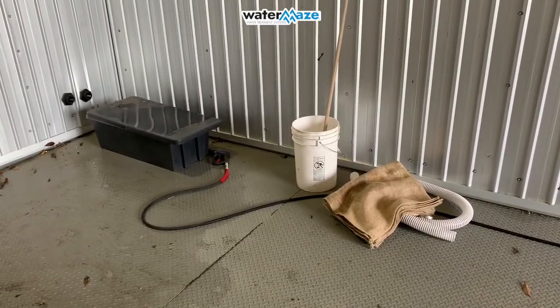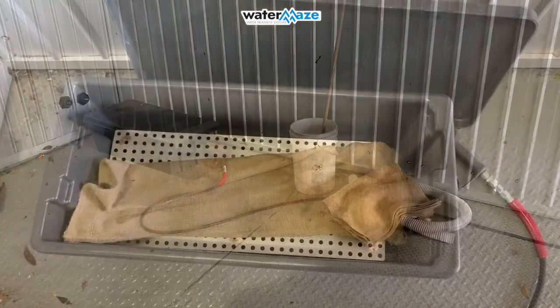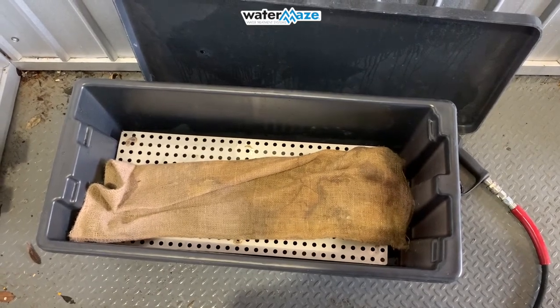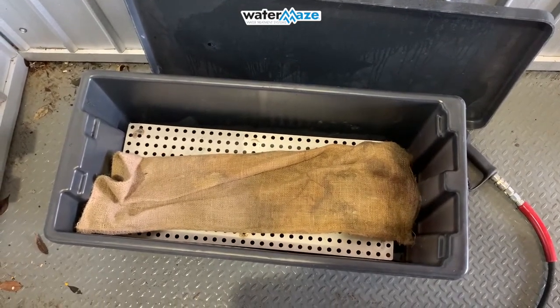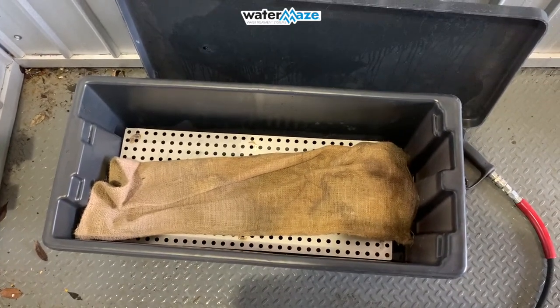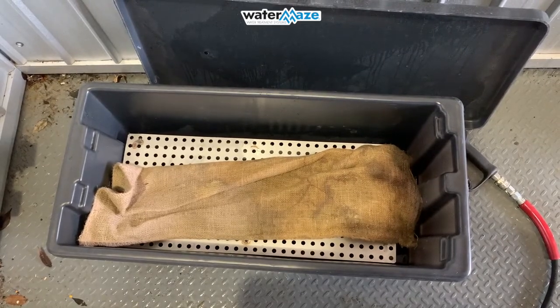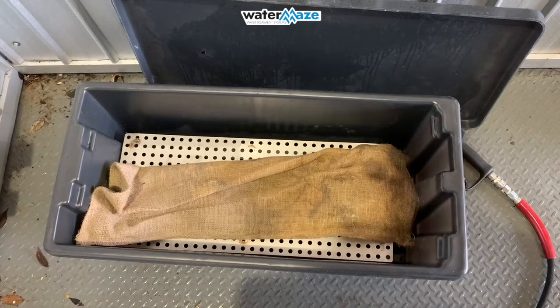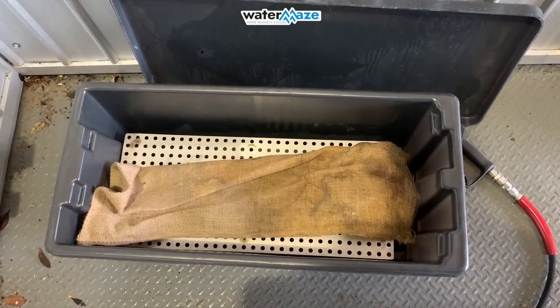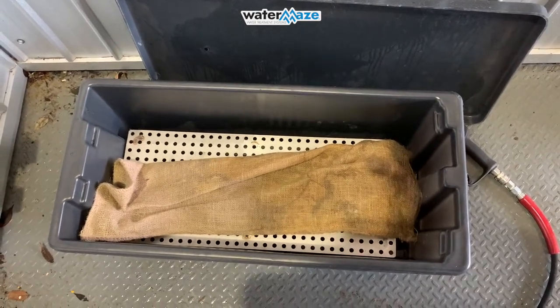Over here on the right you'll see the sludge tub — we'll show you the inside pieces. Looking inside the sludge tub: the water will enter from the left-hand side and go into a hose barbed nipple that will wrap around the burlap bag. The burlap bag is raised up on a stainless steel table to keep it off the floor, and the bucket will be plumbed to dewater itself off the bottom.